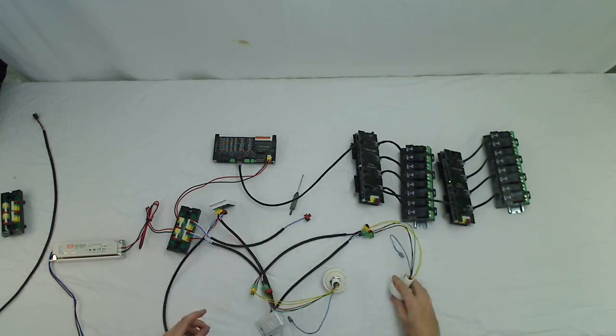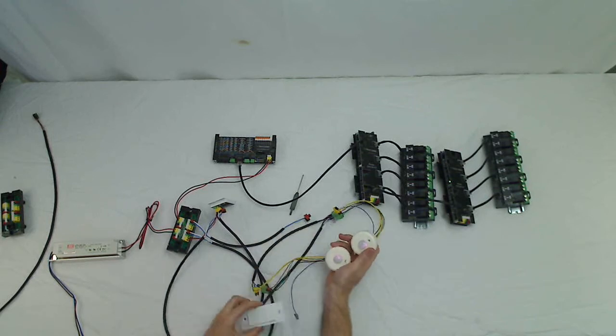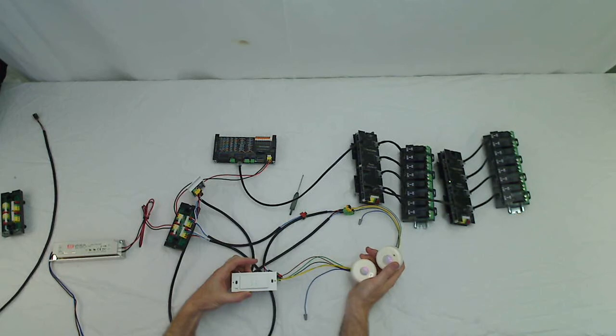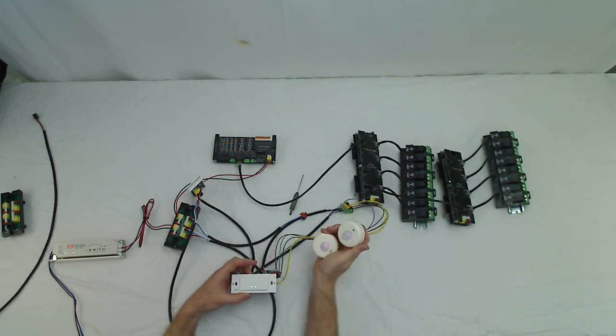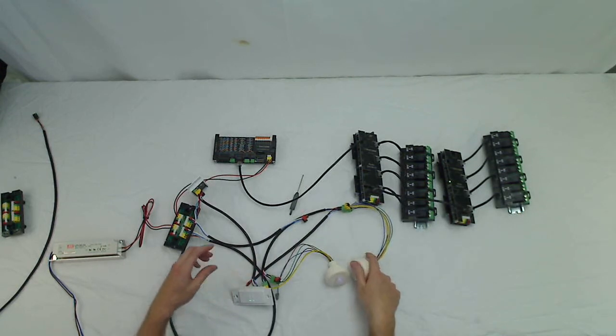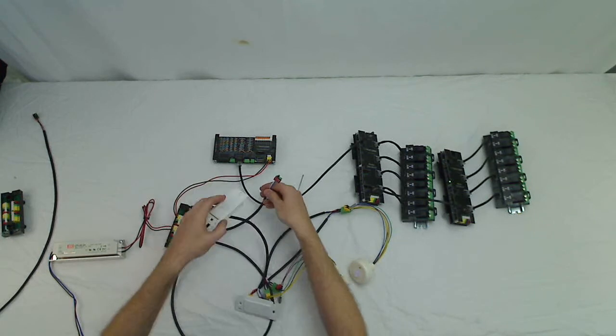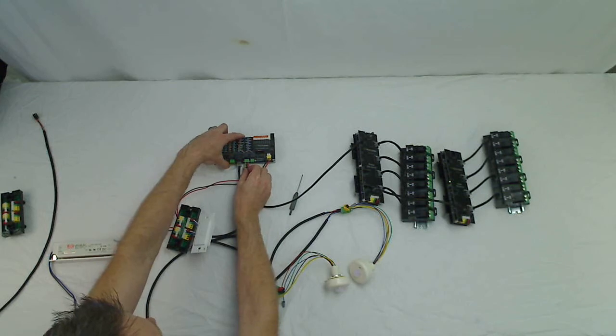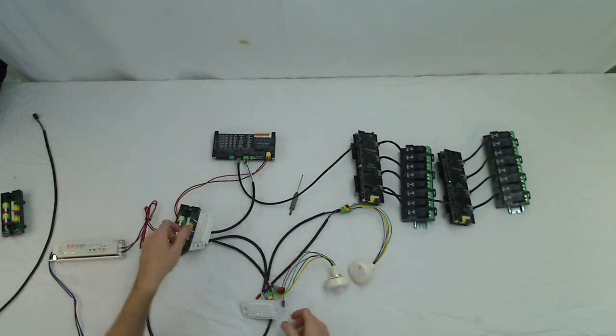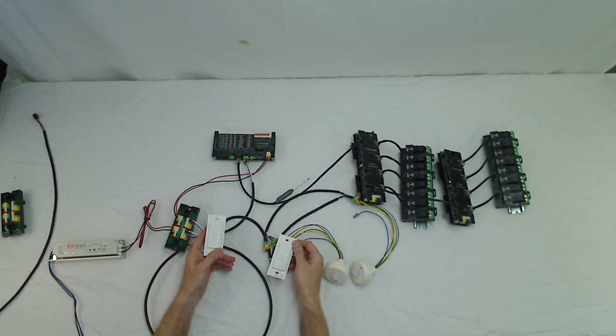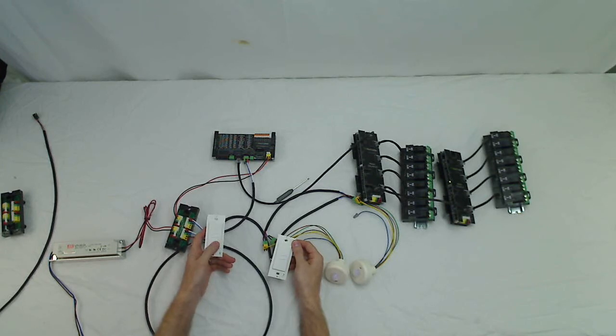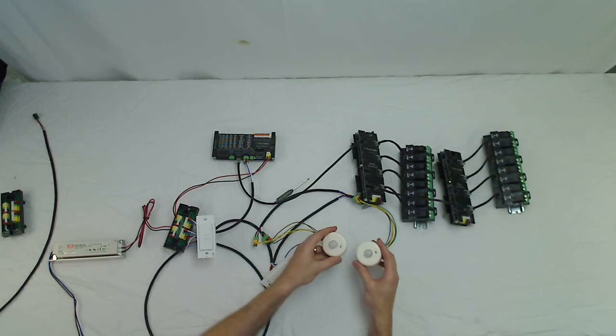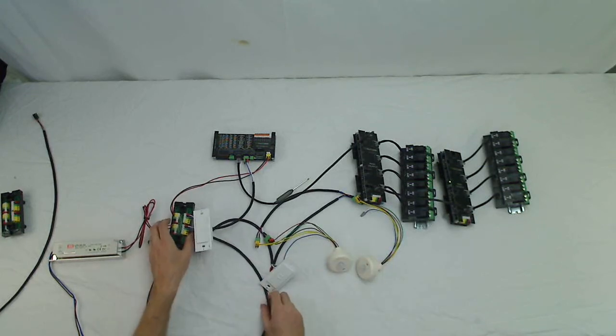Okay. And when sensors and smart stations are powered up, you'll see on the stations, they'll scroll through the LEDs, and sensors will have a solid white or pinkish colored LED on. And they'll remain that way until they're discovered by the controller. So we'll plug in our smart switch connection here. Red-black-green on our smart switch port. And then as the controller discovers them, the LEDs will go out. So station one is discovered, station two is discovered, and both lights went out on our sensors. So these are all discovered.